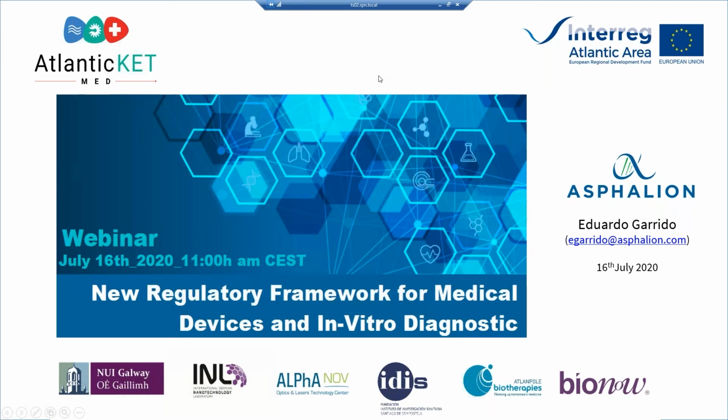Does your notified body automatically become your authorized representative? No. Careful with that. The authorized representative is a figure that is not the notified body. They've got nothing to do with each other. The authorized representative is the entity that is going to be acting as legally responsible for the manufacturer when the manufacturer is outside Europe, let's say the manufacturer is from Japan or from the United States, and they want to bring their product to the European market.